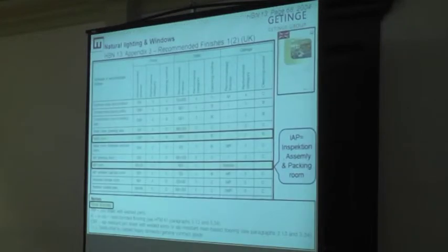And also, there are some environmental things in this HBN guide. There is temperature here. It's probably difficult to see far away, but it's good to know that in HBN 13 there are all the values that might be interesting, like temperature, humidity, and ventilation, and how much lux we need from the lamps in the area. Here is what kind of flooring we need. That is also in the guidelines. So, for example, in the washroom, slip-resistant PVC sheet is recommended. So this is specified for all the areas that can be interesting.